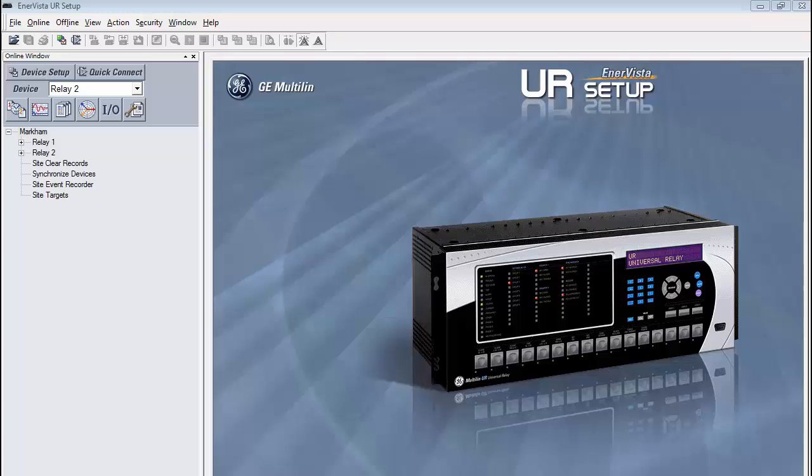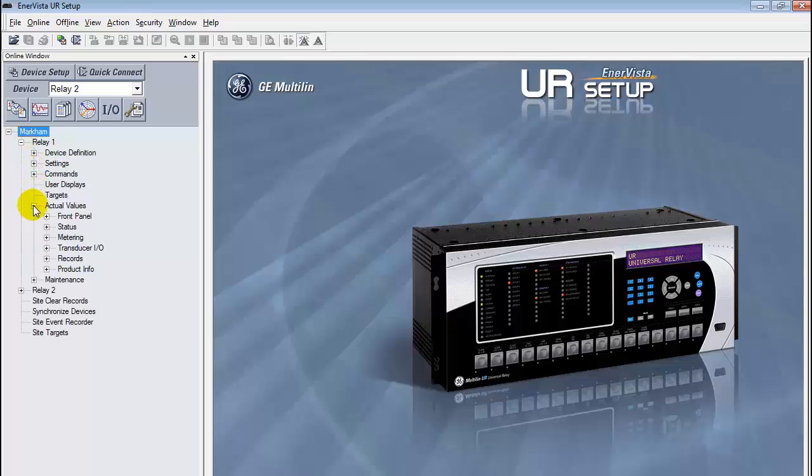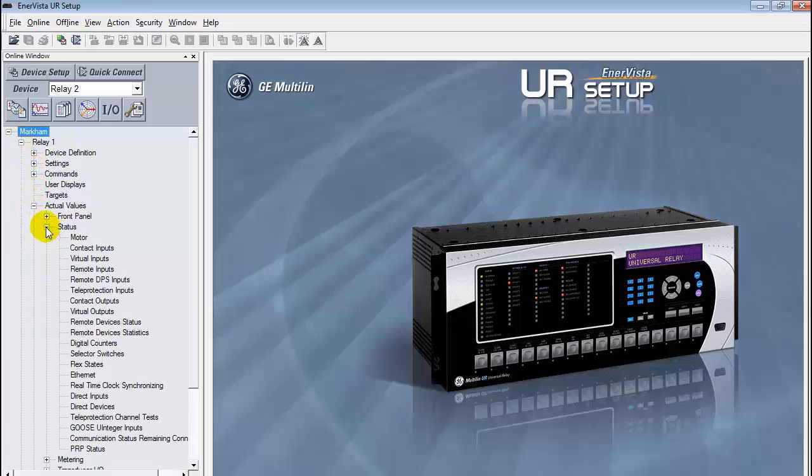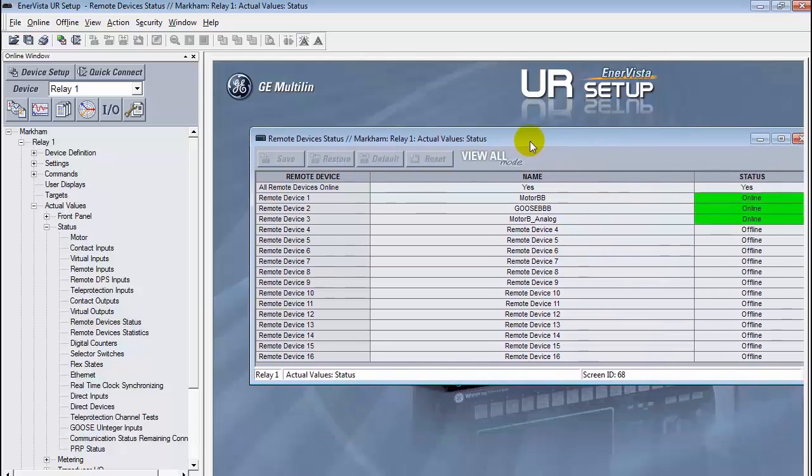Now for the final step, we must validate that both relays are communicating via 61850. Open the remote device status window for each relay. The first three remote devices should be green and read online.